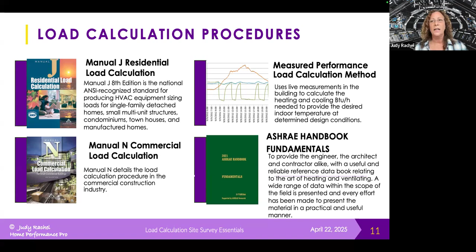I call that the measured performance load calculation method. In some circumstances it's fairly easy to do, but you need the right data logging equipment, the right circumstances, and an actual design day to run it on. So although in some ways it can be easier than the whole load calculation procedure, it has very specific conditions that must be met to use it.